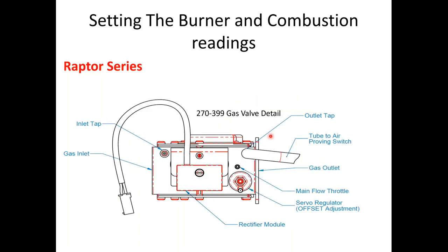So the gas valve on the 270 and the 399 is going to be slightly different. We're not going to have the regulator with the switch. It's going to be a regulator that's screwed to it. There is no on-off switch for it. Your inlet tap's going to be down here. Your throttle screw is going to be moved over a little bit, and your offset regulator is still going to be in that same area. Outlet tapping is still going to go to your air proving switch.